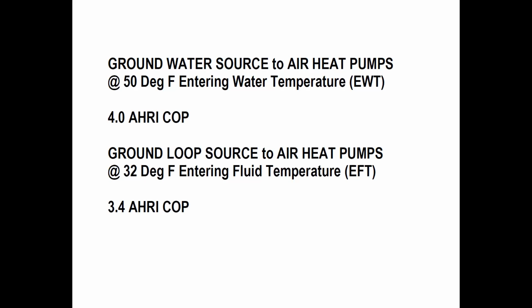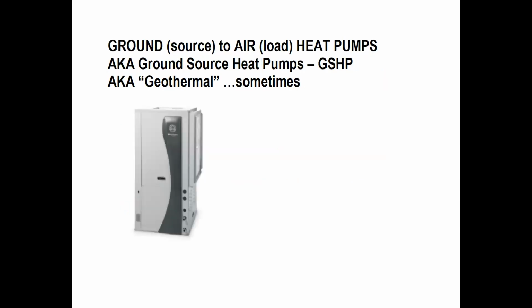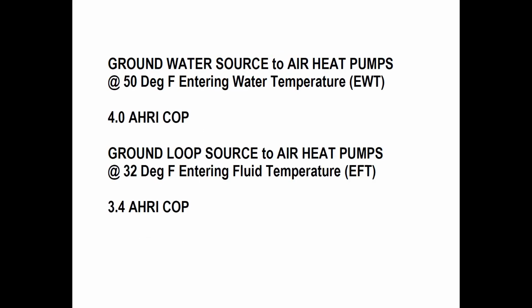Back to the picture that we had, that is the most efficient heat pump, I'm trying to make sure I don't lie about this, for the whole season, because it's a geothermal heat pump. So the outside air temperature is not a variable now. The ground temperature is pretty constant throughout the year. So for these sources, the 32 degrees is a kind of worst case scenario of the fluid temperature that we're coming through. But these efficiencies are for the whole year. It doesn't degrade at minus 13 outside because we're getting the energy from the ground.